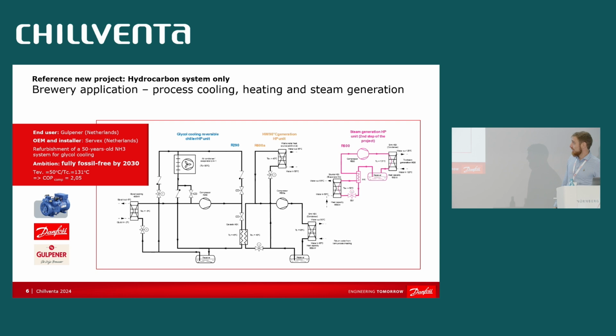One of our projects is in a brewery in the Netherlands, where earlier this year the task was, together with our partners in the Netherlands, to replace a very old refrigeration system for the cooling part, and the target is to replace a gas boiler for the process heating. And we do that with 3 units completely with hydrocarbons. How does it work? The bottom side is a reversible chiller heat pump, where we have a propane system, which is chilling glycol for the brewery.